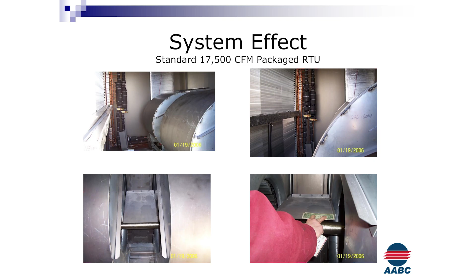So right here is a perfect example of the AMCA charts showing one thing and the manufacturer saying another. And I love the manufacturers, don't get me wrong, but the people that say they're most certain about something are most certainly wrong sometimes, right? I've had some in my experience. So with this, the test and balance firm was able to get the 17,500 CFM package rooftop unit back under control, the building open and occupied and ready for service. And all it took was a little vortex breaker. And I still don't know if the manufacturer went back and altered their design. I'd like to think that they did, but I find it hard to believe that this is the only one in the country that was doing that.